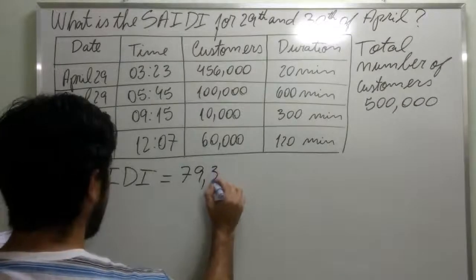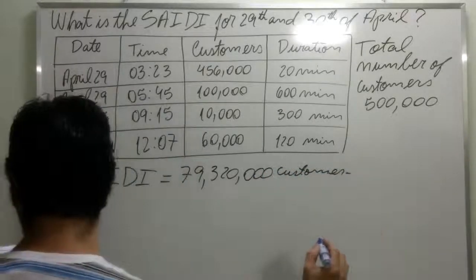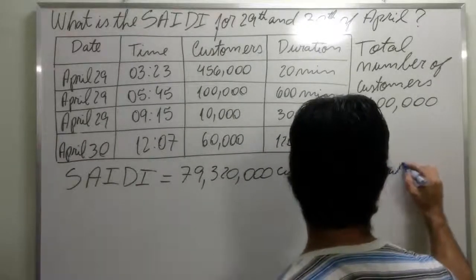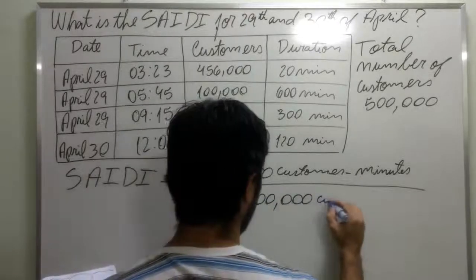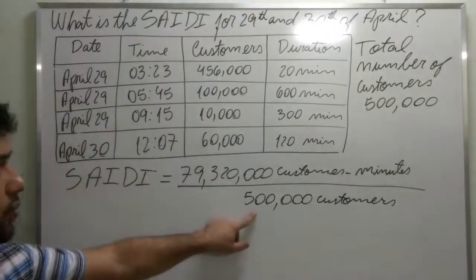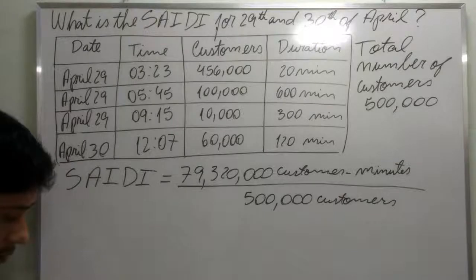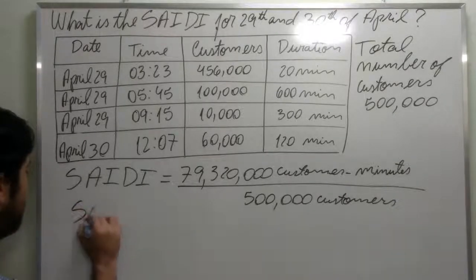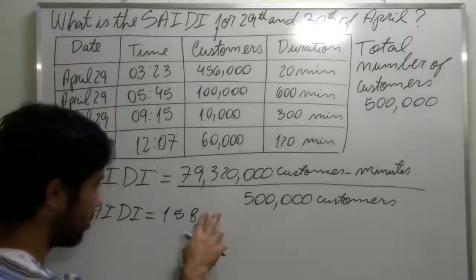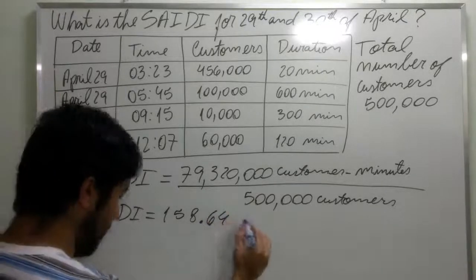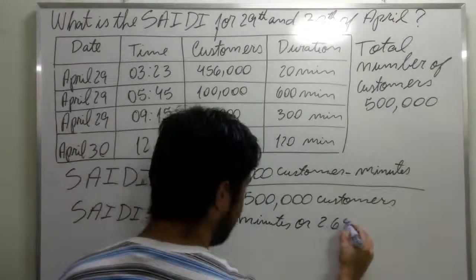I already did the calculation and found a total of 79,320,000 customer minutes, divided by 500,000. After doing this math, we find that our SAIDI will be 158.64 minutes, or 2.64 hours.